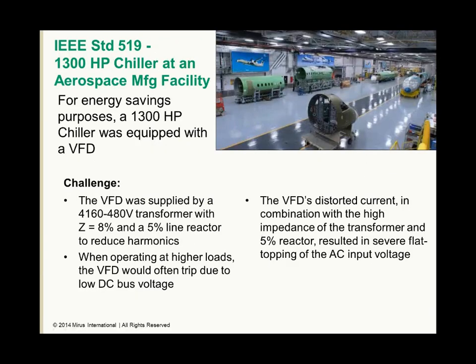In a Bombardier Aerospace facility near Toronto, a 1,300 horsepower chiller was equipped with a variable speed drive to reduce energy consumption. In an attempt to prevent the negative effects of harmonics, a 5% impedance reactor was included with the installation. However, this added impedance in combination with the already high impedance of the step-down transformer, which was 8% impedance, resulted in a voltage drop that prevented the chiller from reaching its rated capacity.